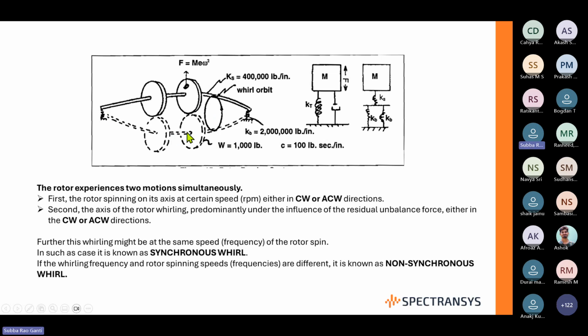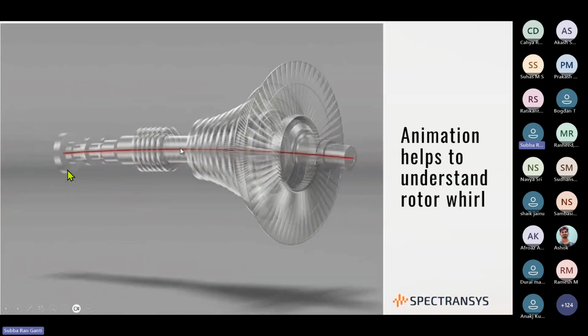This whirling motion is principally seen at the bearings. While the entire rotor experiences whirling motion, most of the time we are not interested in or cannot measure or visualize that. But when we measure the movement of the rotor within the bearings itself, that's what we try to get. When measuring at the bearing, it is basically called the orbit.